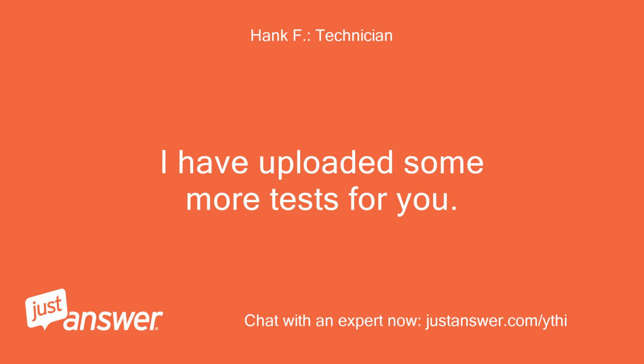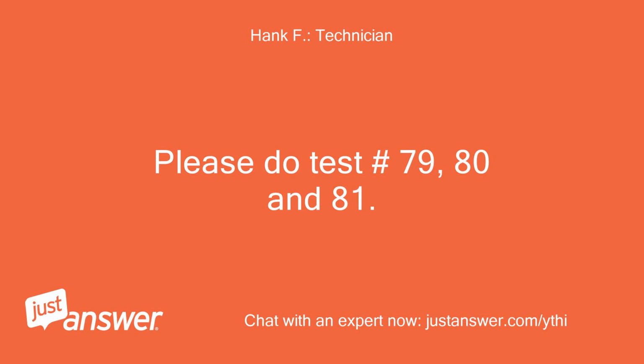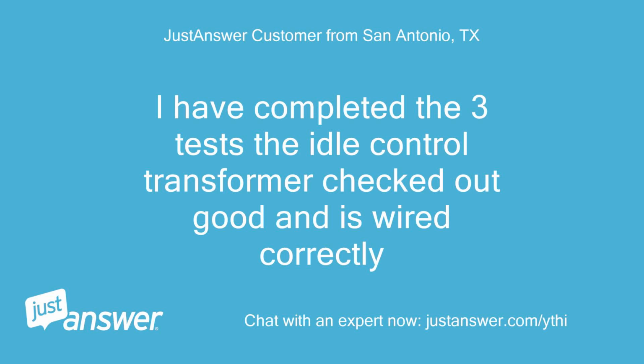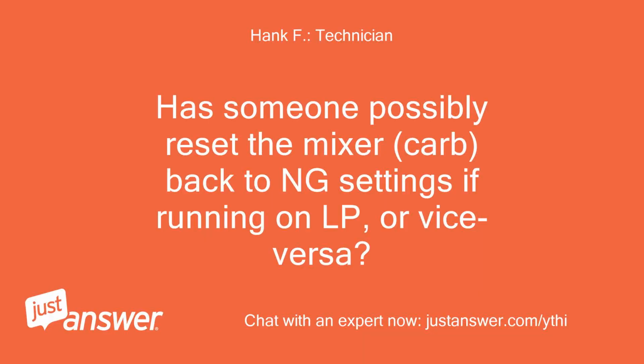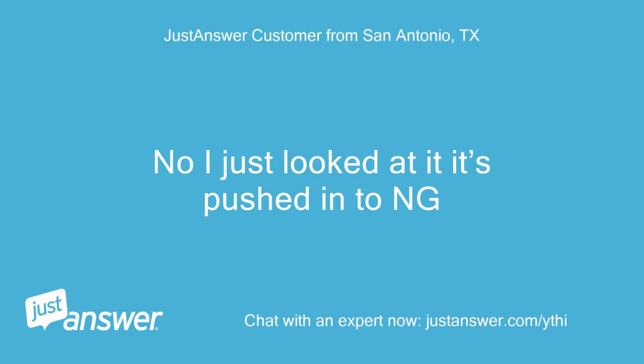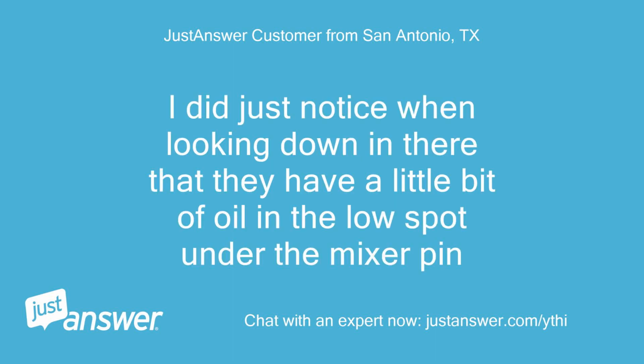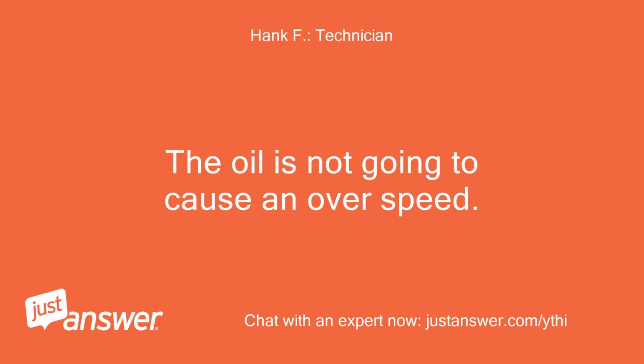I have uploaded some more tests for you. Please do tests number 79, 80 and 81. I have completed the 3 tests. The idle control transformer checked out good and is wired correctly. Has someone possibly reset the mixer, carb, back to NG settings if running on LP, or vice versa? No, I just looked at it, it's pushed into NG. I did just notice when looking down in there that they have a little bit of oil in the low spot under the mixer pin. The oil is not going to cause an overspeed.